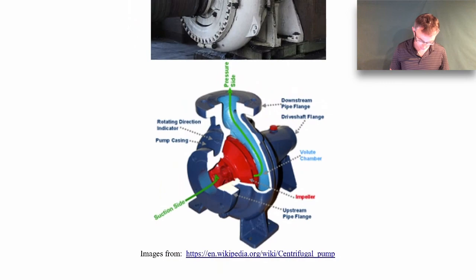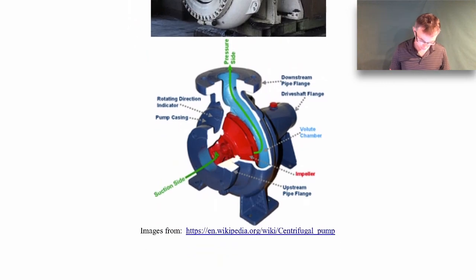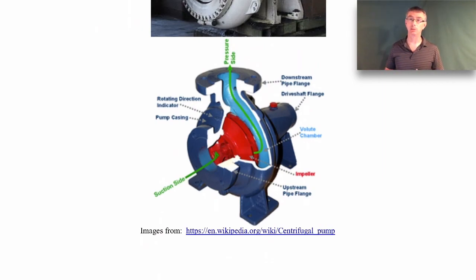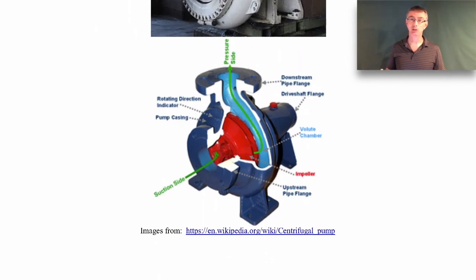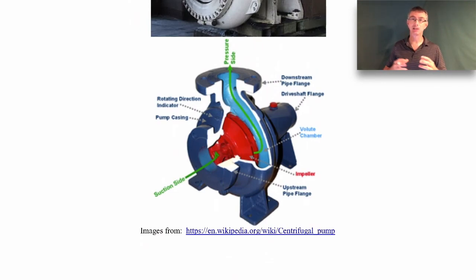Looking at the interior of the pump, you have what's known as the suction side — the fluid comes in here at the low pressure side. The whole purpose of a pump is to increase the pressure in the fluid. It's a pressure rising device: it comes in at low pressure and should go out at high pressure. The flow rate through the pump doesn't change — the flow rate at the inlet and outlet is exactly the same, just from conservation of mass. A pump does not suddenly speed up the flow; what it does is change the pressure from inlet to outlet.